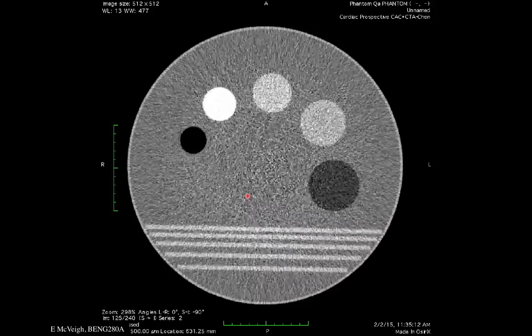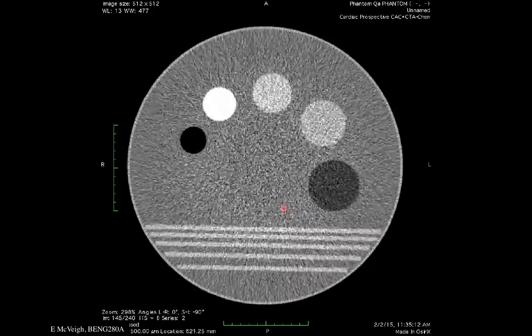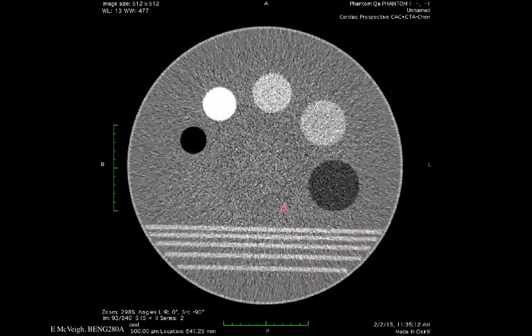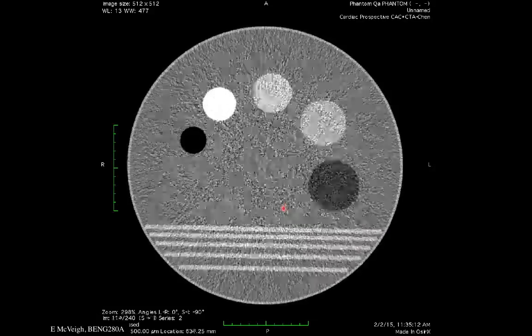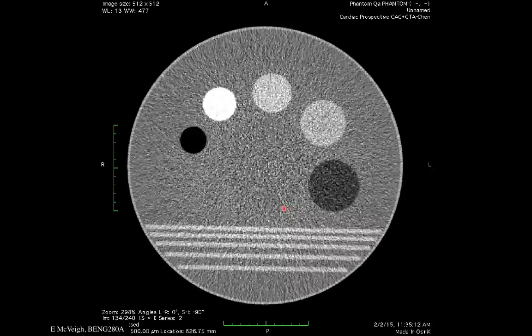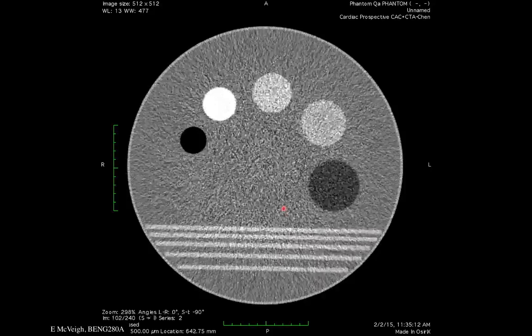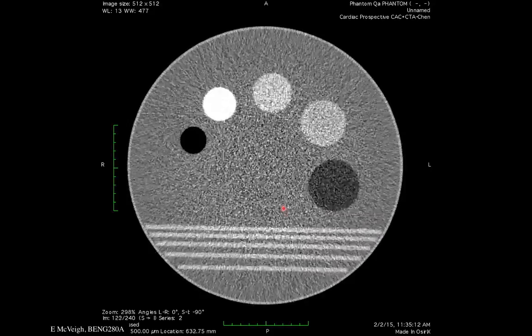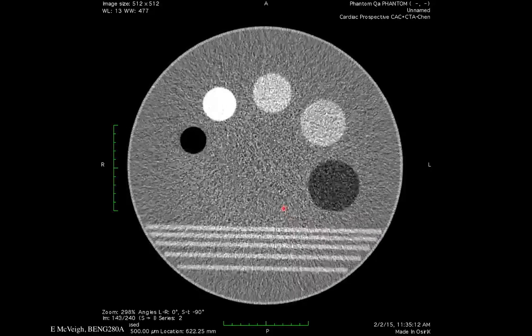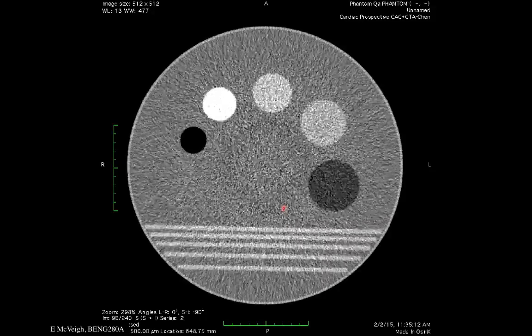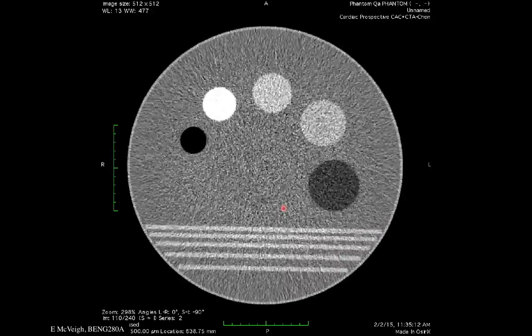And this is why CT signal-to-noise analysis is a little tricky, right? Because it's not just a noise field that is like white, ergodic, Gaussian noise. It has structure, right? And so you're competing with this noise structure when you're trying to detect things.